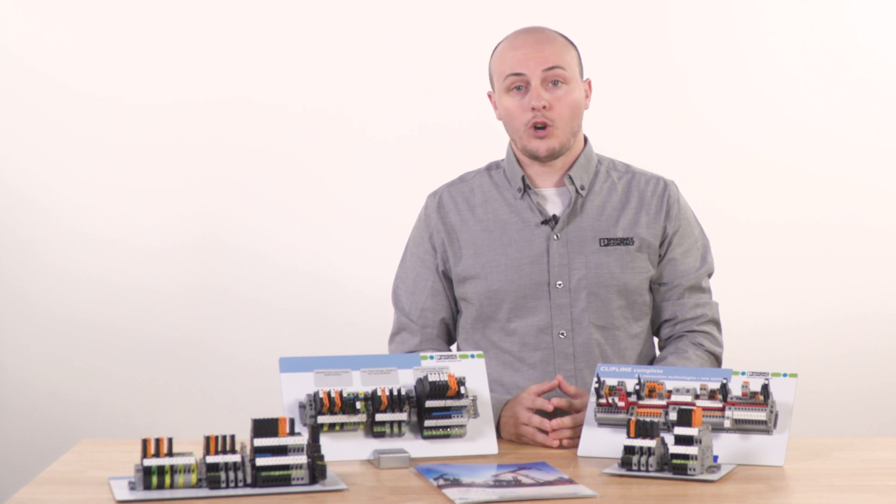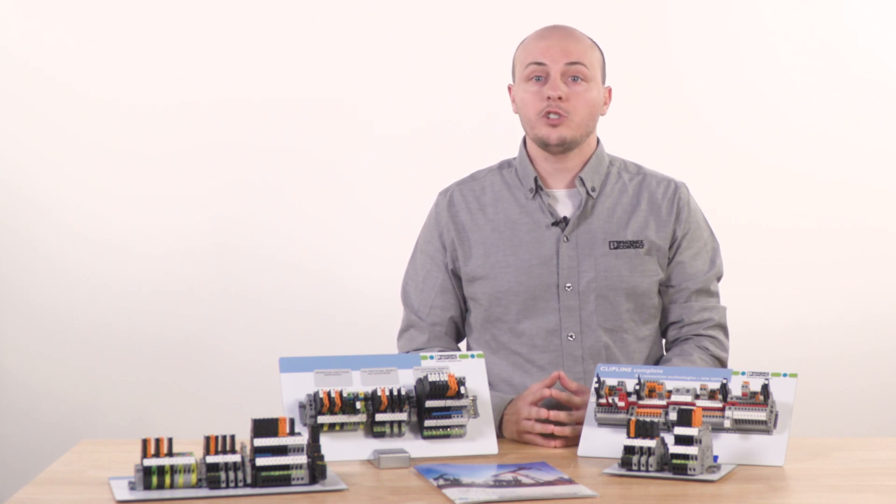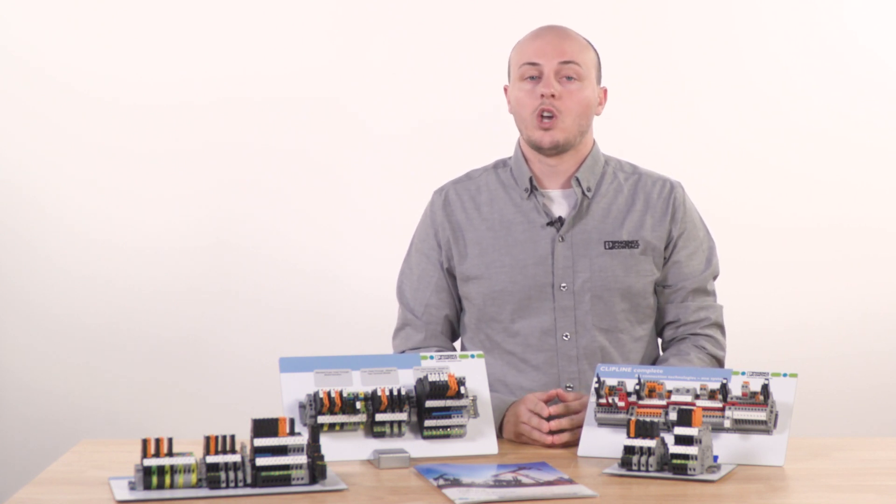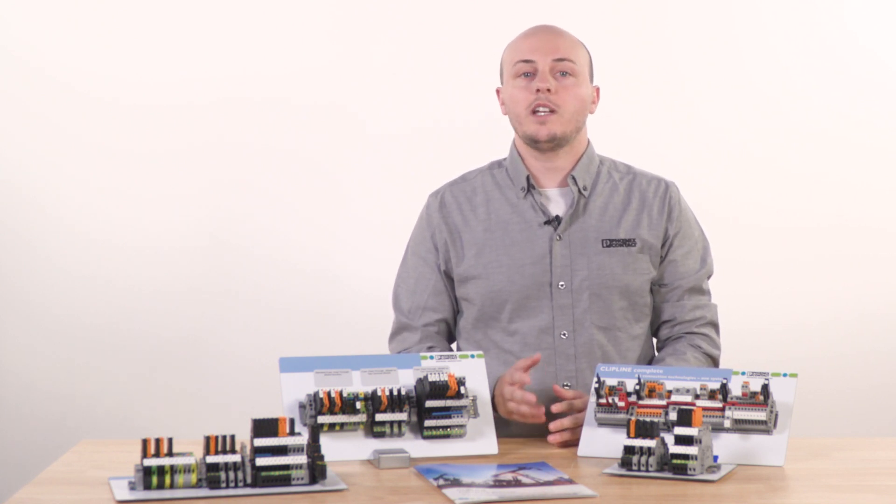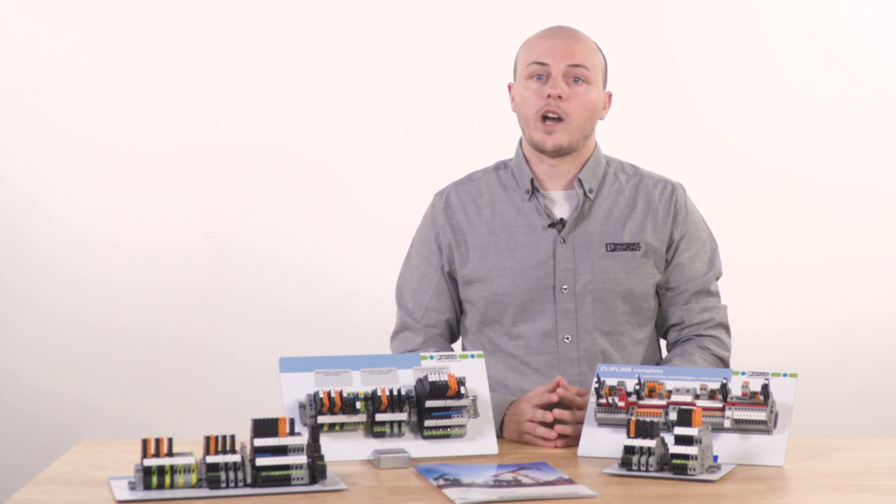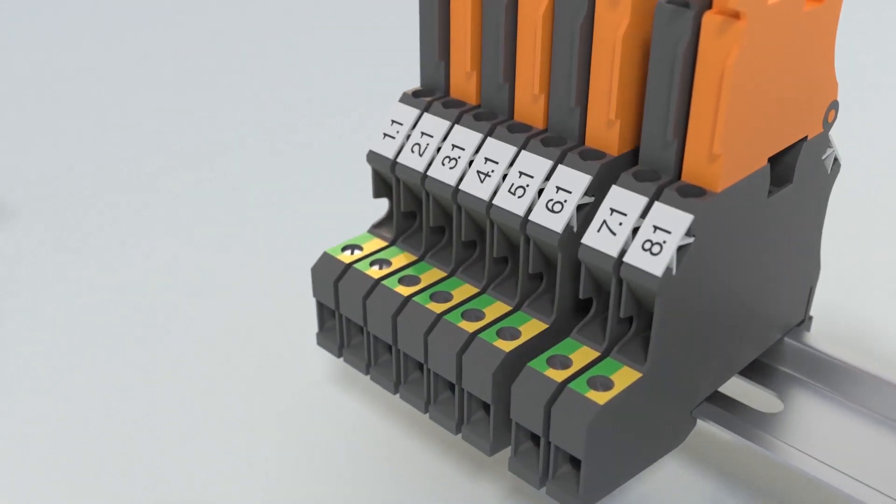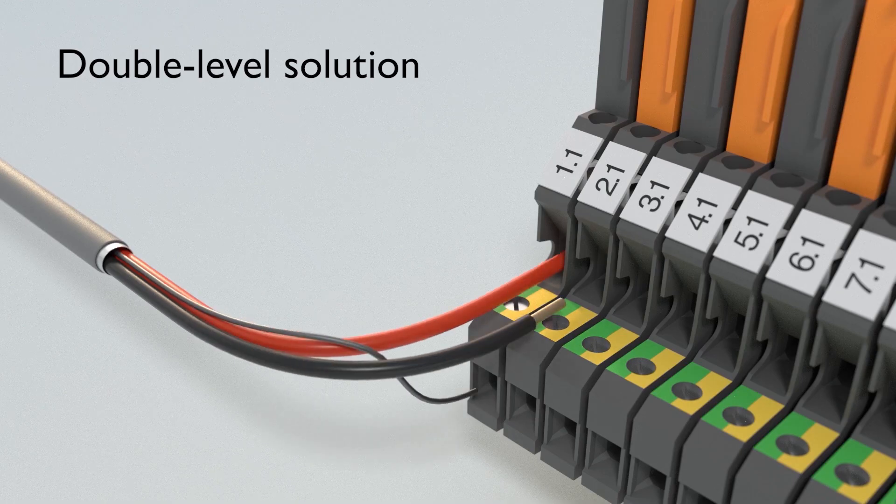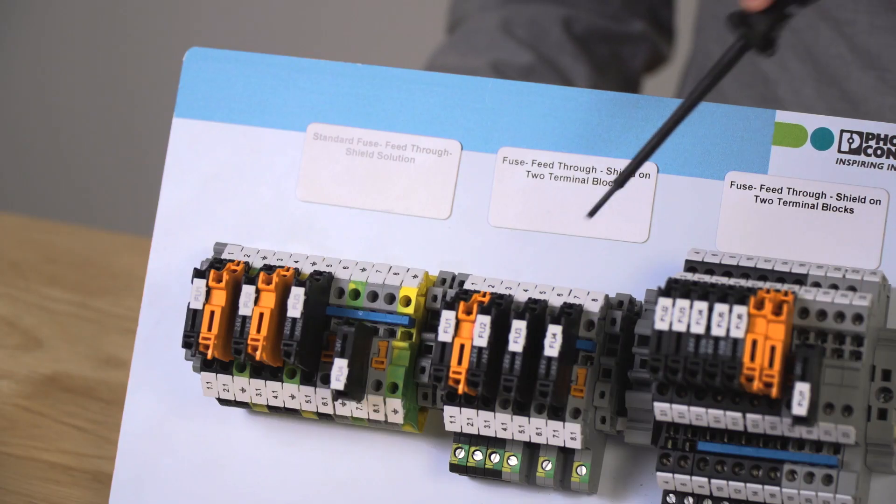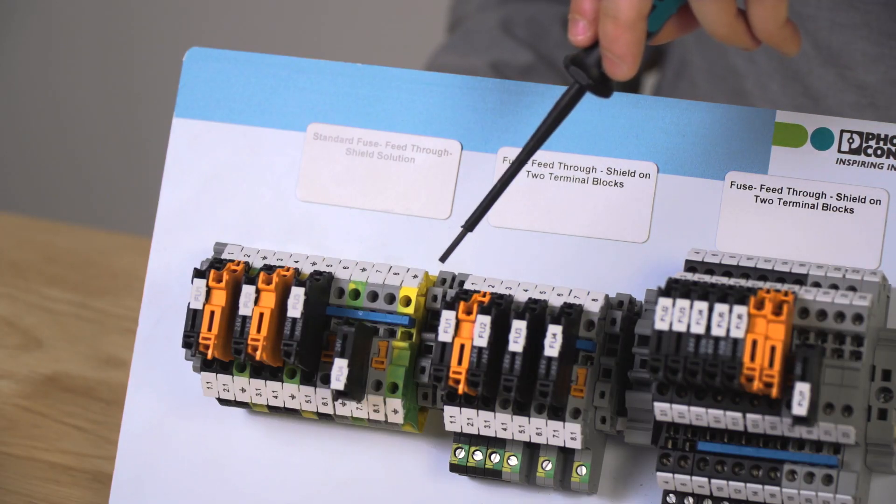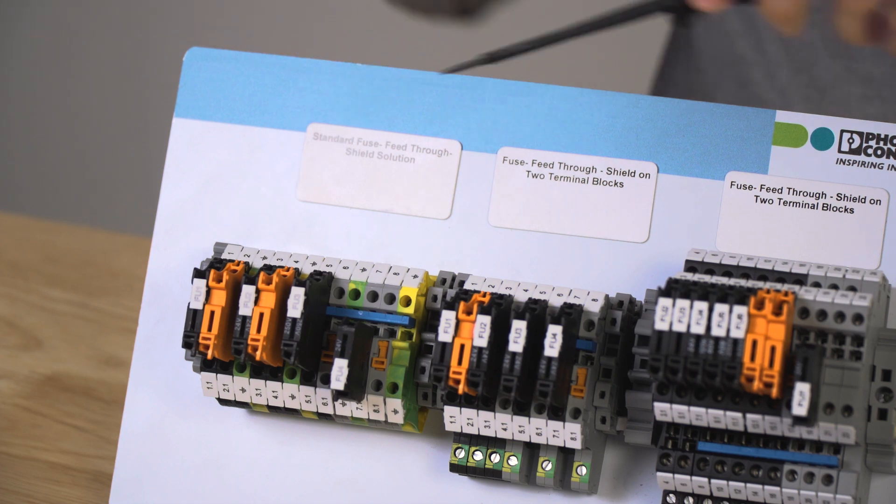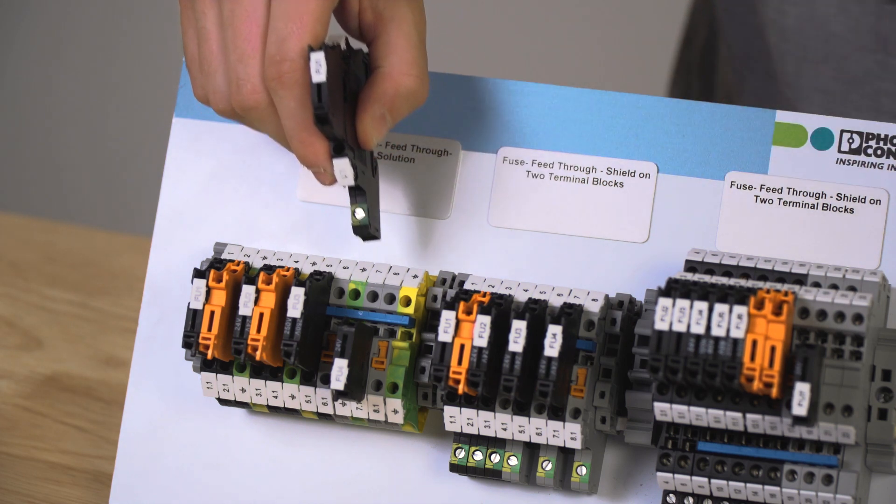As an alternative, Phoenix Contact also developed a series of terminal blocks with an integrated ground foot to attach the shield wires. This solution allows for the elimination of ground terminal blocks that you see in the standard single level solution. This results in a 33% space saving along the DIN rail.